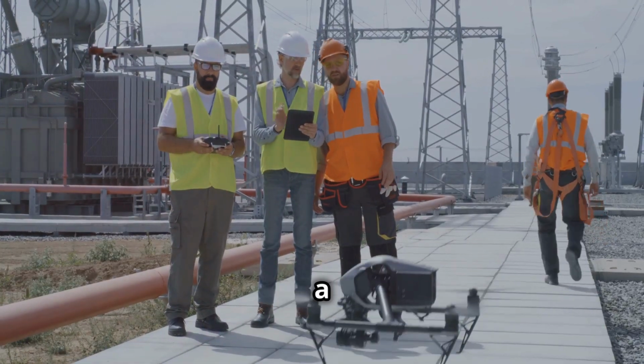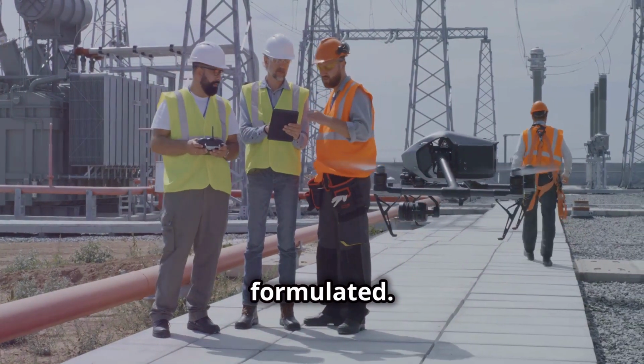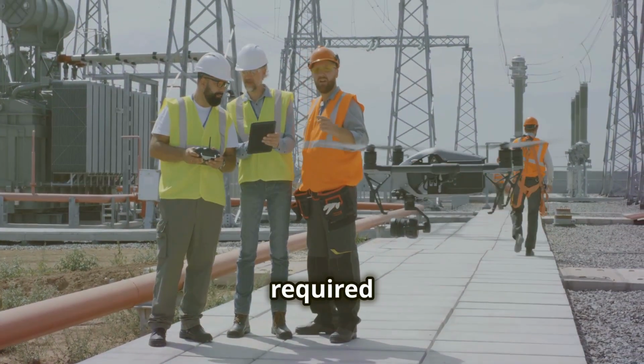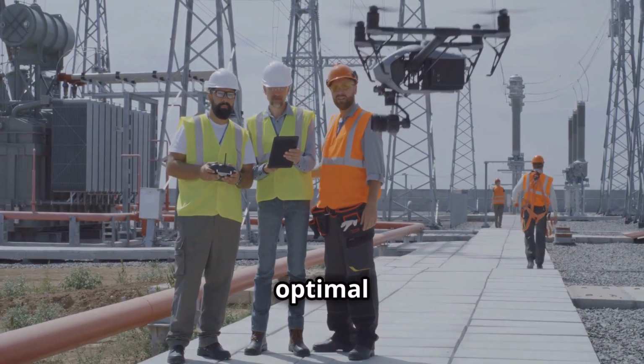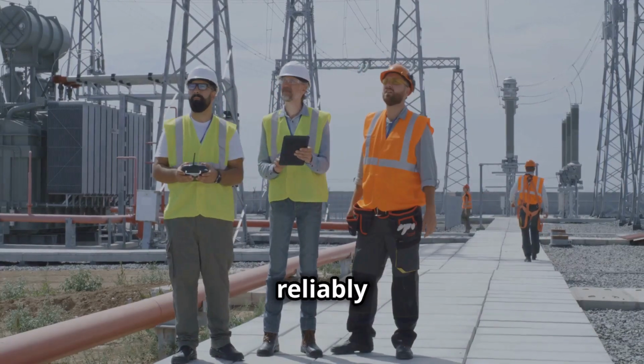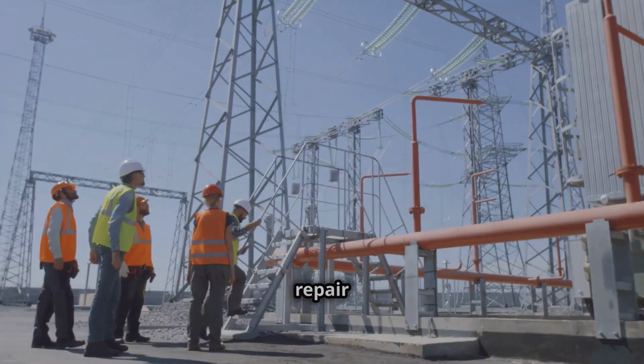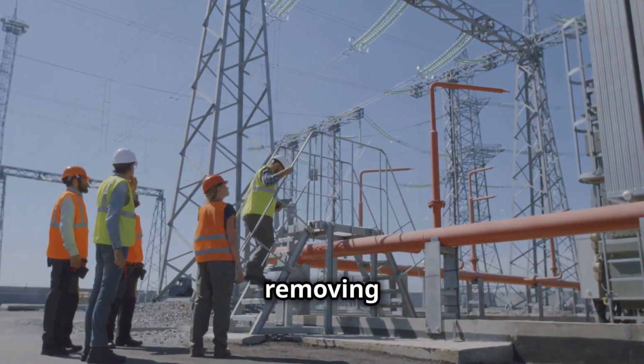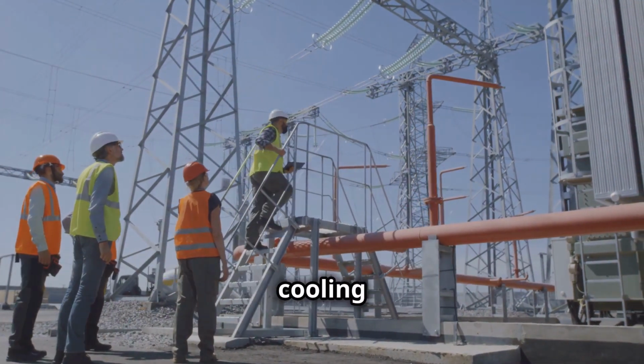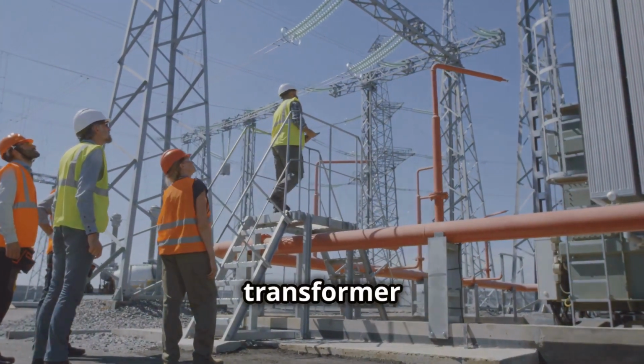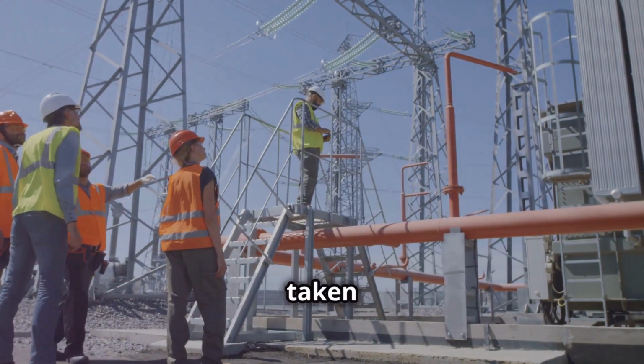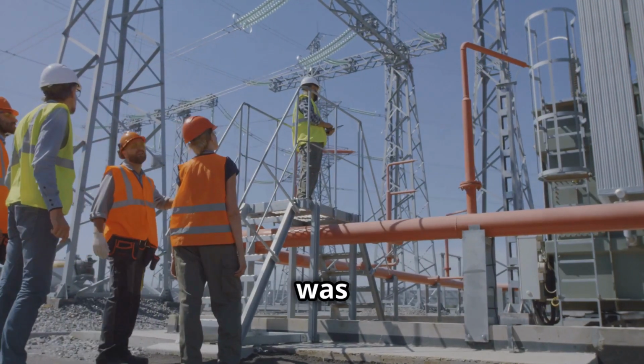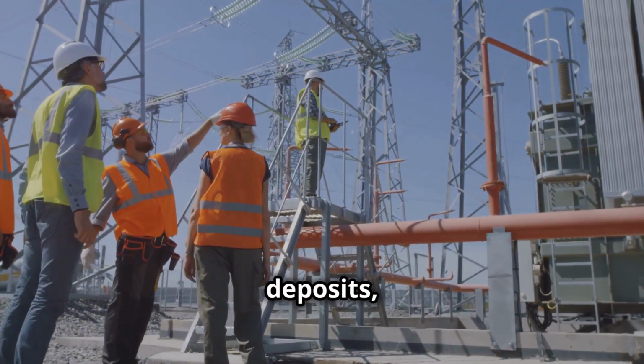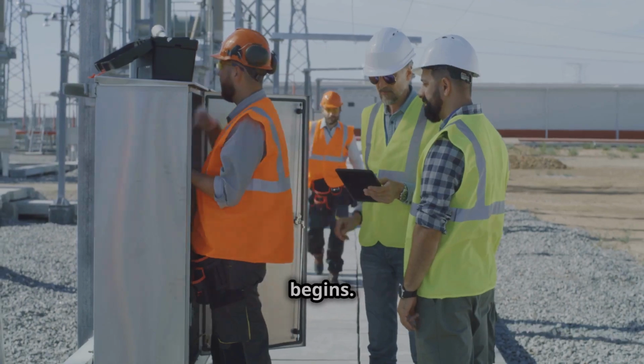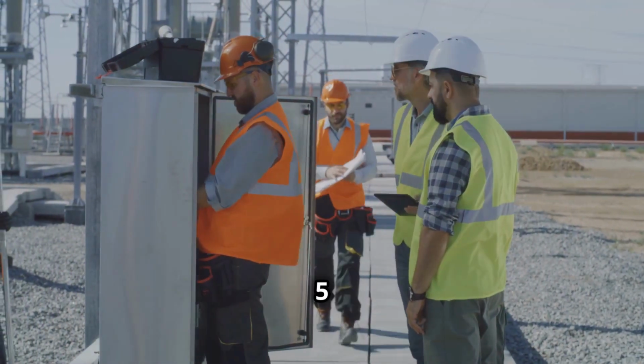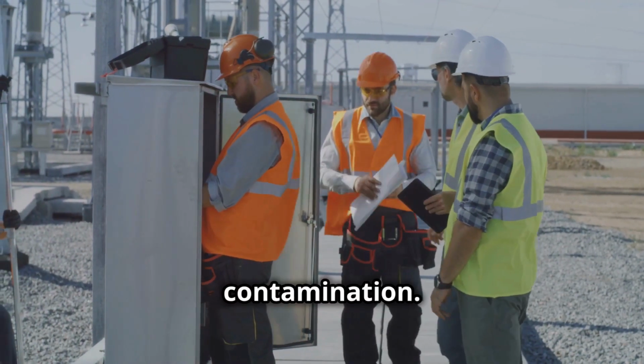After the assessment, a detailed repair plan is formulated. This plan outlines the steps required to restore the transformer to its optimal condition, ensuring it can function reliably once reinstalled. The repair process may involve removing external parts including bushings, cooling fins, and the oil tank. The transformer core and windings are taken apart for further testing. If it was contaminated by water or carbon deposits, a deep cleaning process begins. This step takes 2 to 5 days depending on dirt and oil contamination.